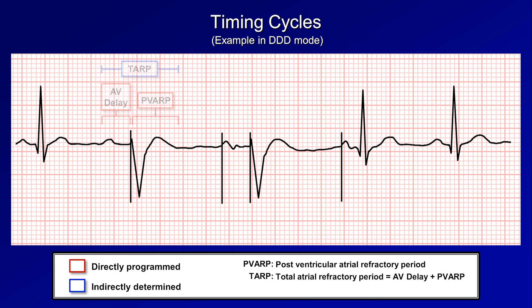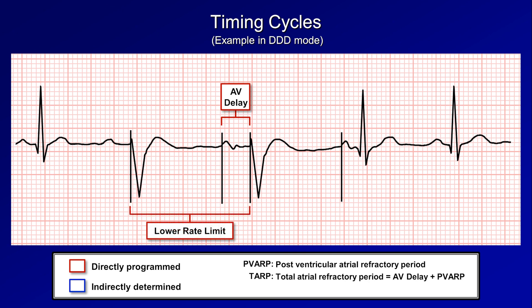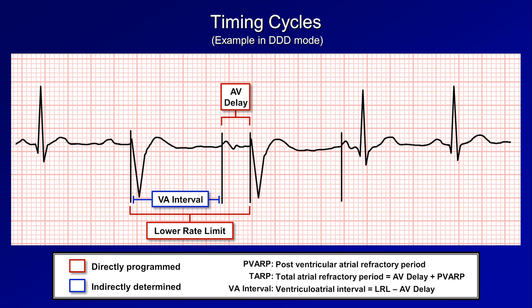For the next beat, because there was no intrinsic P wave sensed, the pacemaker delivers an atrial pacing spike, followed by the AV delay, and then a ventricular pacing spike. The interval between these two successive paced ventricular beats is defined by the lower rate limit. From a pacemaker's perspective, it's more logical to think of this in terms of milliseconds — in this case about 1040 ms. The timing of the atrial spike is based on the VA interval, which is indirectly determined as the difference between the lower rate limit in milliseconds and the AV delay.